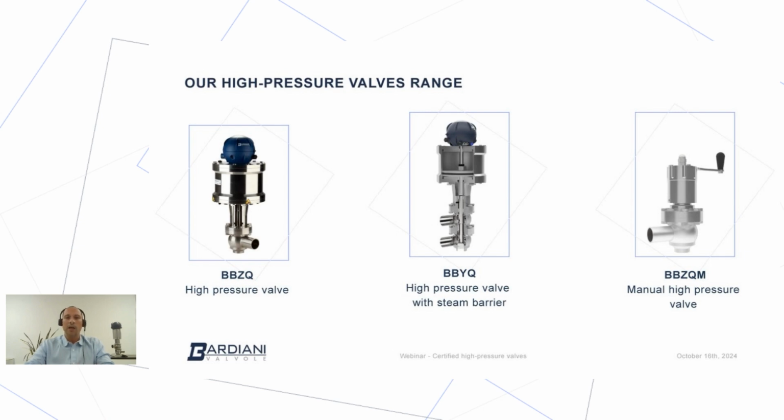So for this reason, when we approach an aseptic concept applied to a high pressure valve, the only solution is to have a steam barrier. Steam barrier, very simple concept, is a stainless steel metal ring which is located between the part in contact with the product and the outside and the shaft, with a continuous flow of steam at minimum 121 degrees Celsius. We are sure that there's a physical barrier between the product side and the external atmosphere.